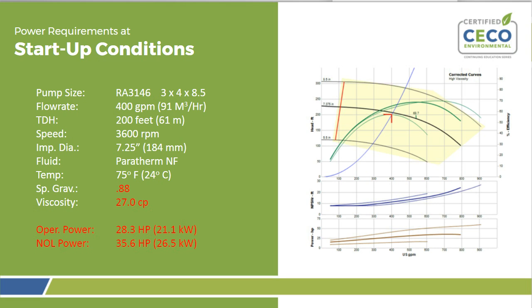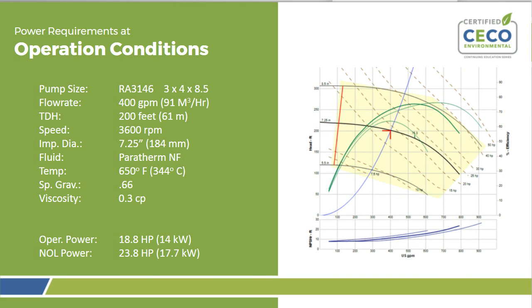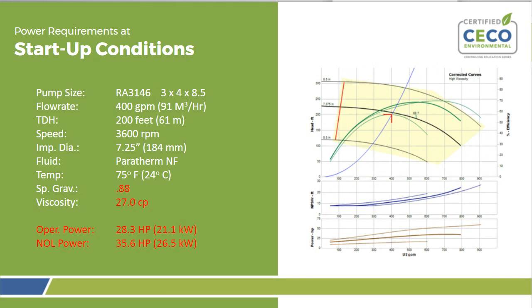At that temperature, that Paratherm NF has a specific gravity of 0.88, much heavier than the 0.66, and a viscosity of 27 centipoise, significantly different than the 0.66 and the 0.3 centipoise that was at the operating conditions. Plot this same condition on a curve, and the operating power suddenly jumps to 28.3 horsepower. The non-overloading power jumps to almost 35.6 horsepower.